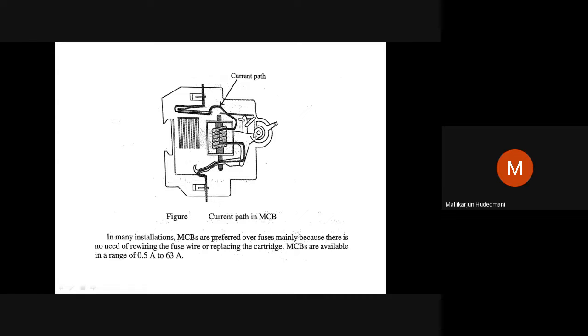So you can explain: this circuit breaker works on the principle of current. Whenever the current flowing through this particular device, which is specially a bimetal strip arranged here, exceeds the current rating of that, automatic heating will take place, and a small deformation of the metal contact makes the circuit isolated. Because of that, the break of circuit, the mechanical movements, because it is deforming means what? Micrometric displacement occurs. This metal automatically makes its movement. That movement is encased by the mechanics available here.